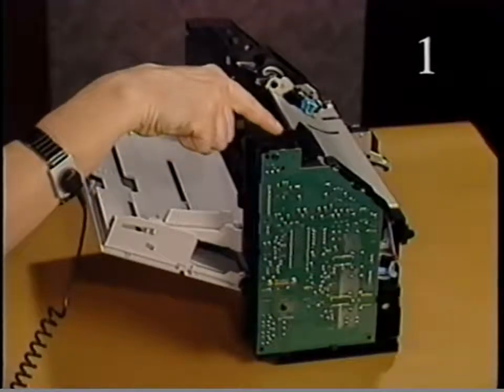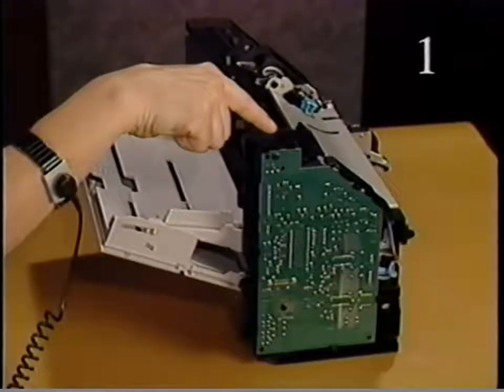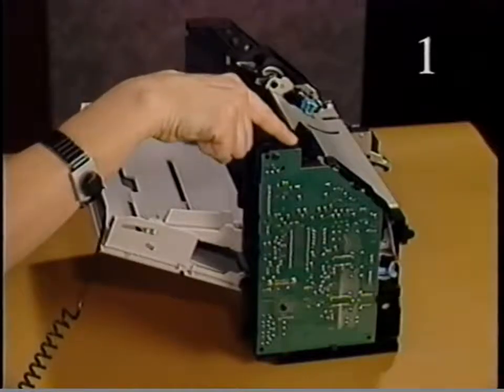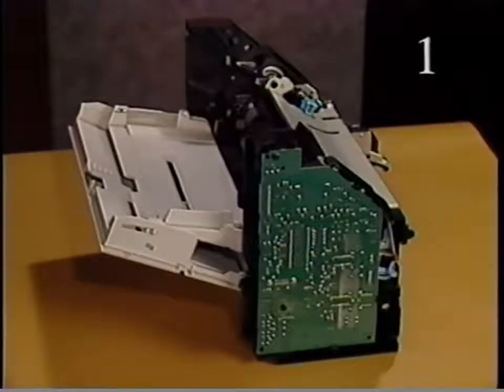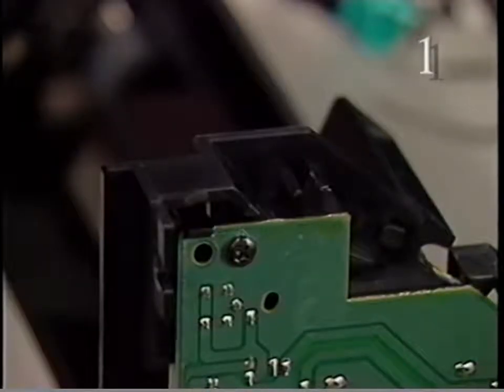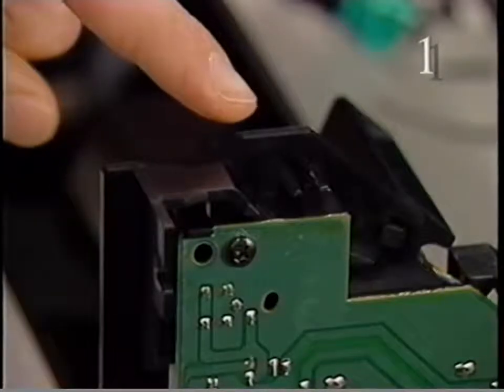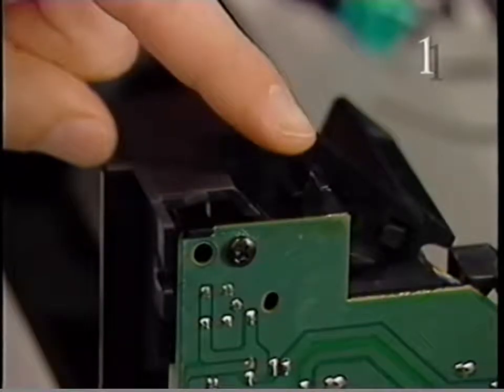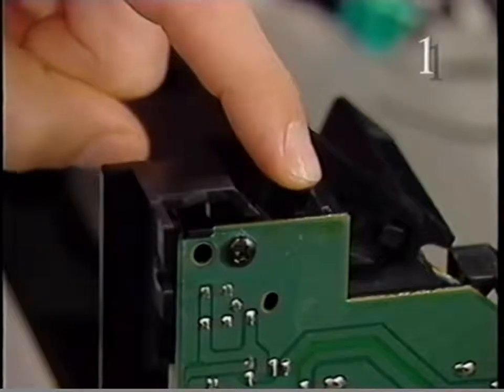Here are the top cover interlock switch SW601 and switch actuator. When the top cover is open, the actuator opens the switch, cutting power. When closed, the cover interlock arm on the top cover depresses the actuator, closing the switch and restoring power.